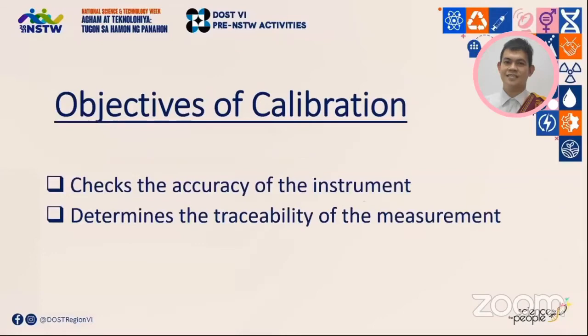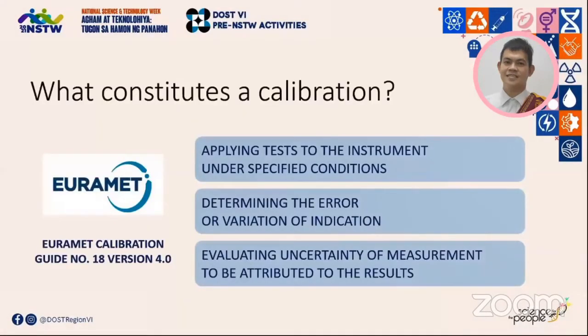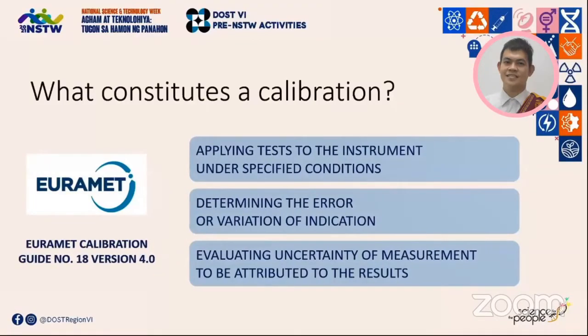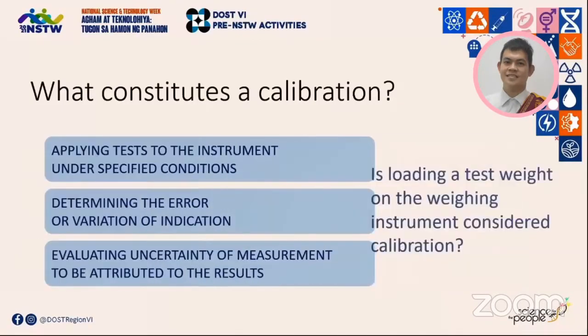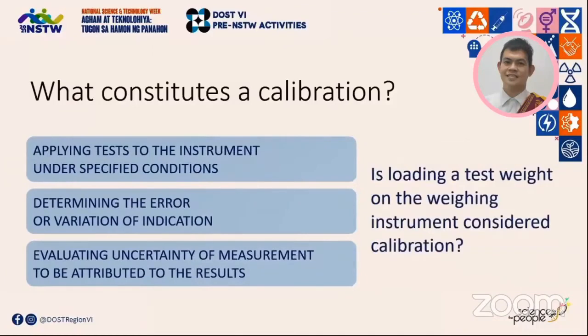In order for a process to be considered a calibration, the following must be met: the first is the application of tests to the instrument under specified conditions; the second is the determination of the error or variation of indication; and the third is the evaluation of uncertainty of measurement to be attributed to the results. With this in mind, simply loading a test weight on a weighing instrument is not considered a calibration, as only one of these conditions is met.